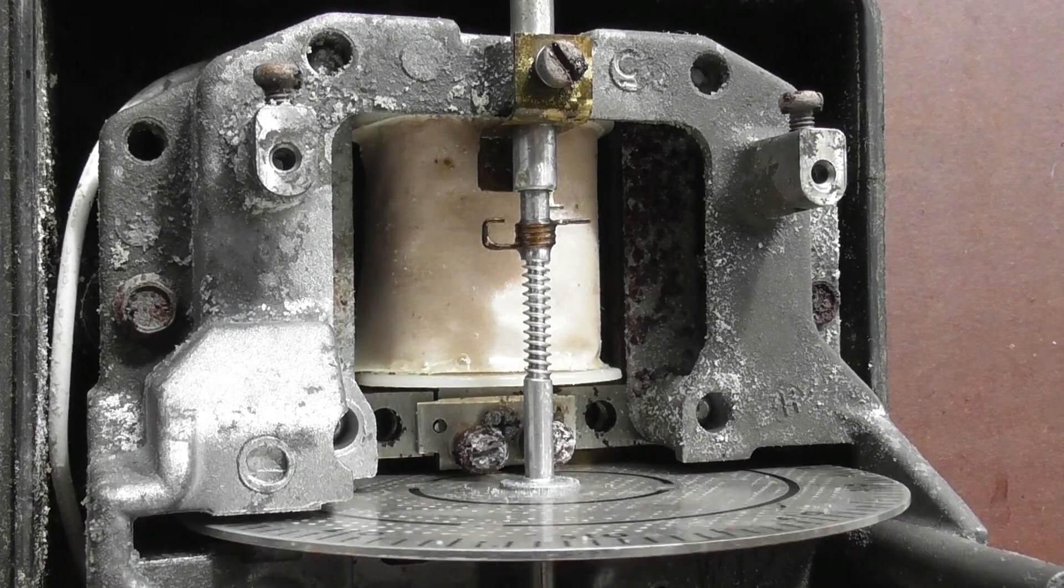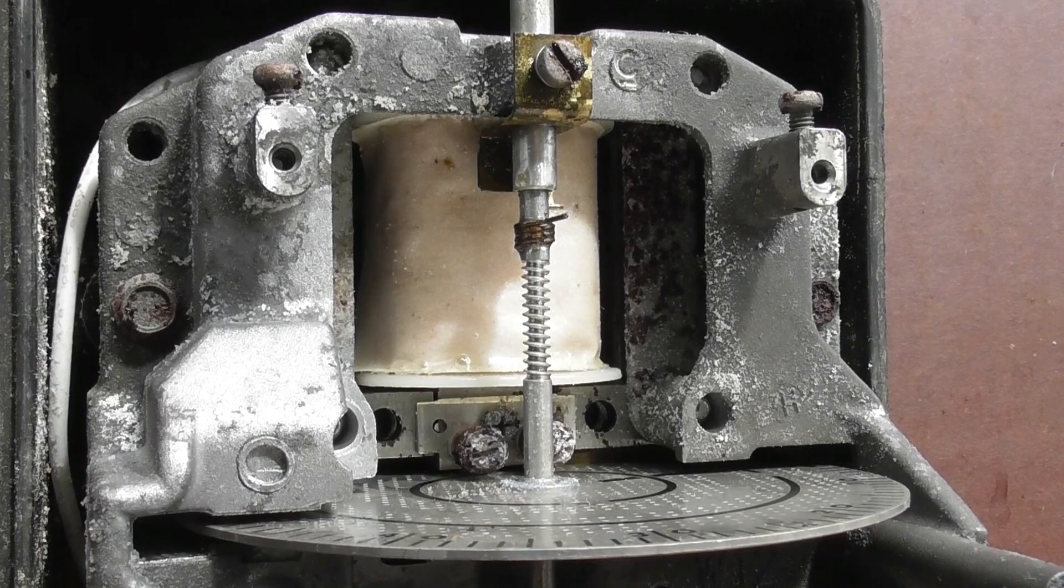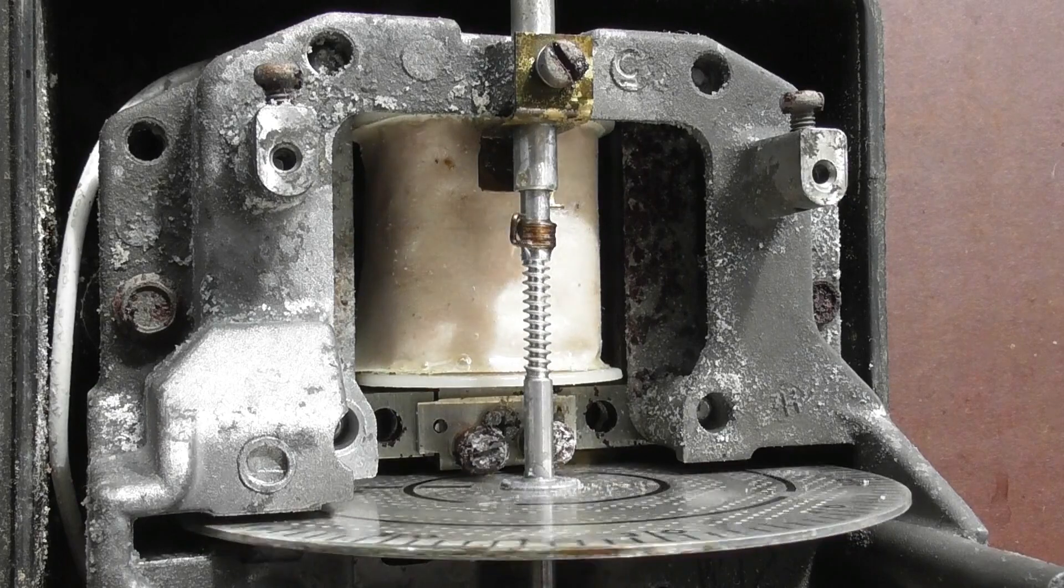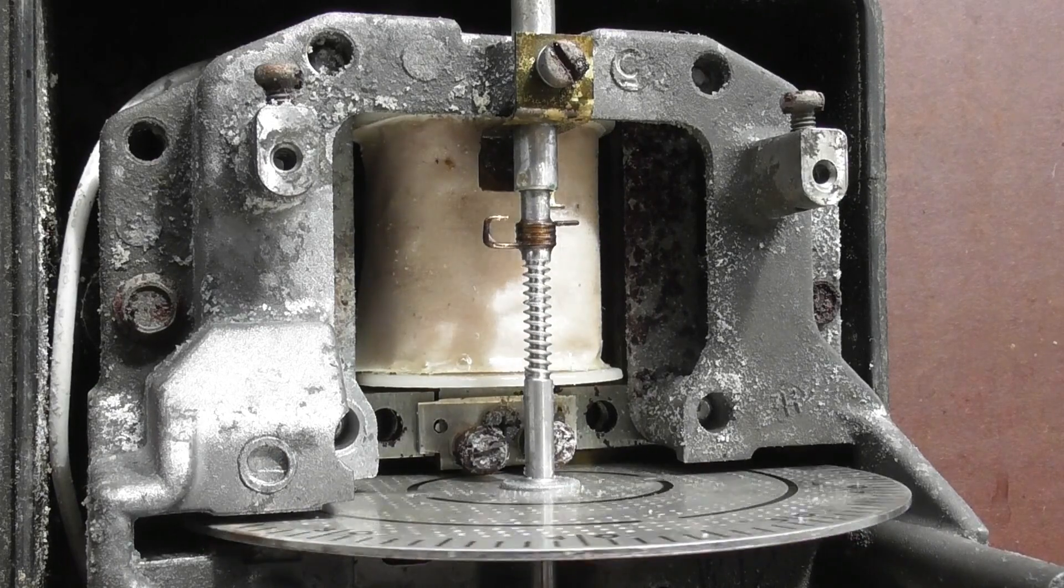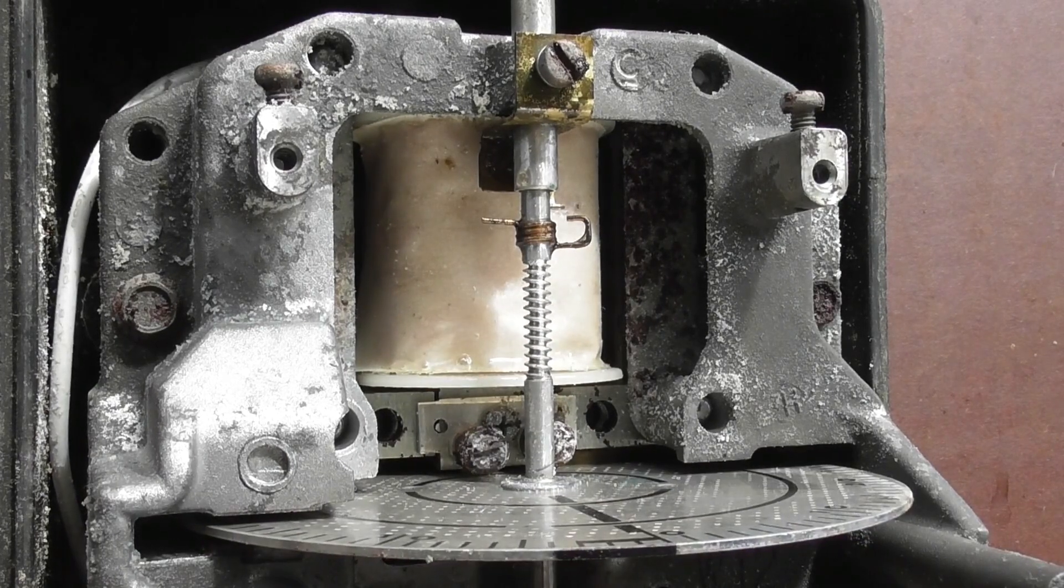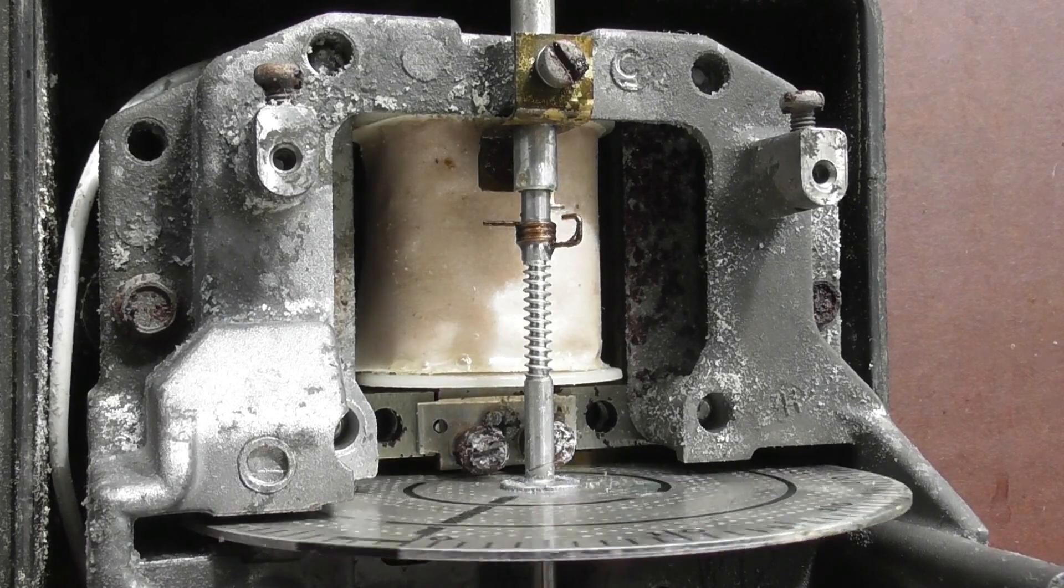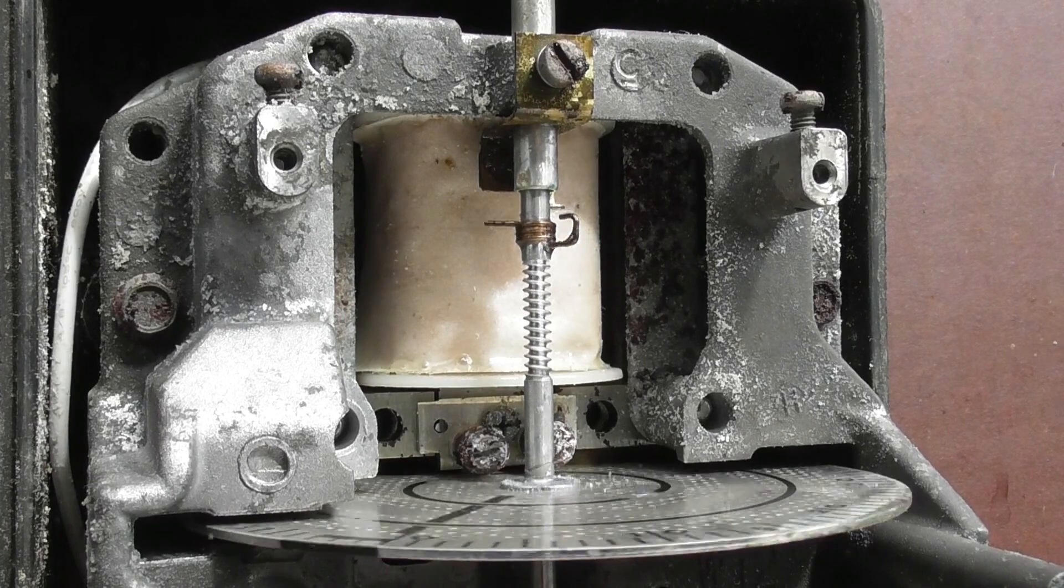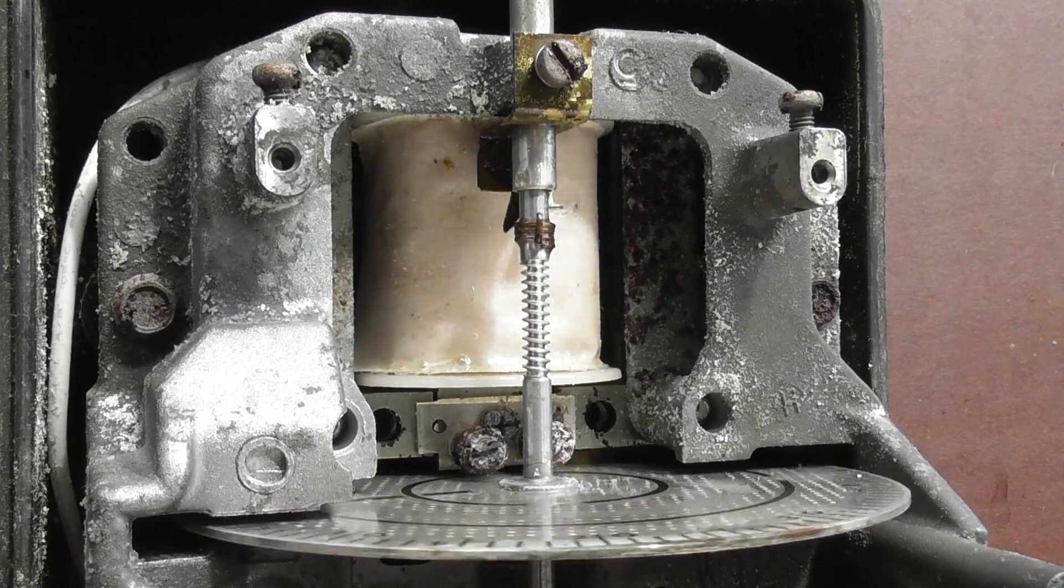I've got an electronic meter too and I'll show you how that works. So it just does the forward, backwards, click. It imposes more or less no burden on the disc, so it's not a problem accuracy-wise. There we go. So that's the last shot on this device, and then I'll show you an electronic meter.